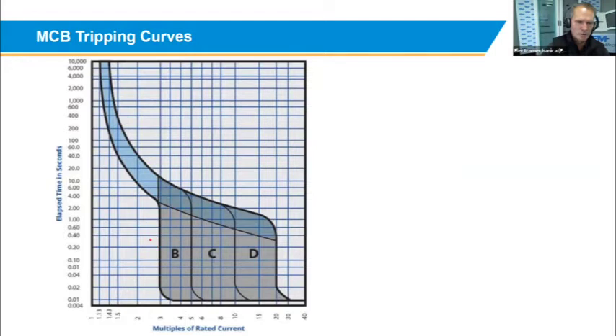So as mentioned, the B curve will allow you 3 to 5 times inrush current. So for example, we'll take a 100 amp miniature circuit breaker on a B curve. You want to protect an electric motor, and the rated current of that motor is 100 amps. On startup, a motor will take 7 to 10 times the inrush current. So if it runs at 100 amps, when you start that motor up, it will go to 700, 800 amps, which will fall into this category here somewhere, and it will go into the short circuit application, or the magnetics, of the B curve, and the B curve circuit breaker will trip, and you will think that there's a problem on your installation. In the meantime, it's just because the B curve circuit breaker cannot handle that amount of inrush.